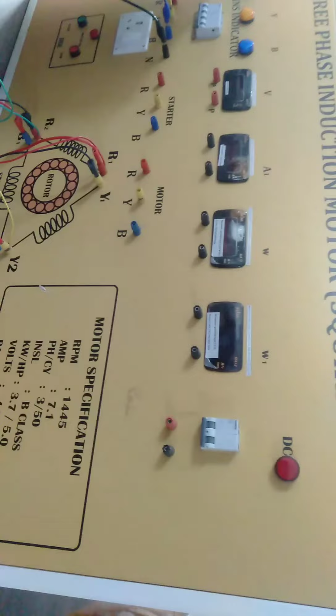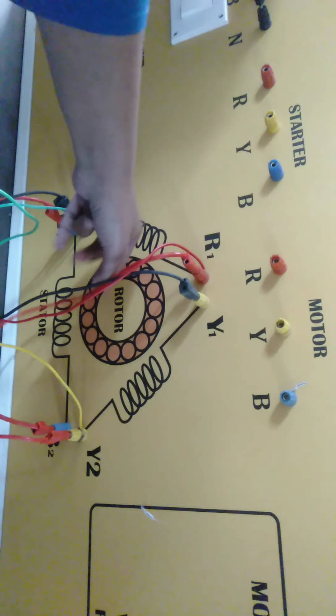If you see here, this is the motor winding - stator winding - and this is the rotor winding. The stator winding has to be connected in delta form. You all know that in delta, the end point of each winding should be connected to the starting point of another winding, so let us see how we connect this externally.